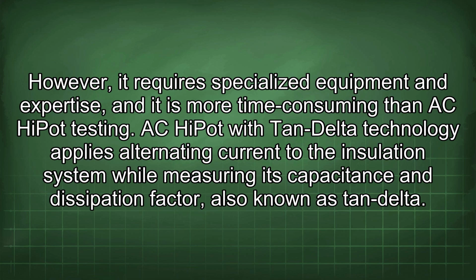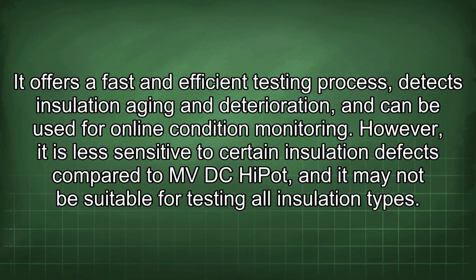AC HiPot with tan delta technology applies alternating current to the insulation system while measuring its capacitance and dissipation factor, also known as tan delta. It offers a fast and efficient testing process, detects insulation aging and deterioration, and can be used for online condition monitoring. However, it is less sensitive to certain insulation defects compared to MVDC HiPot, and it may not be suitable for testing all insulation types.